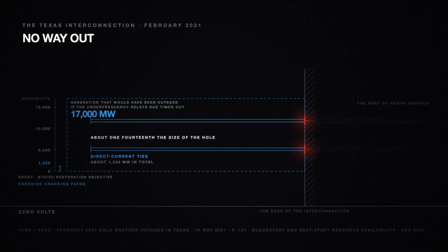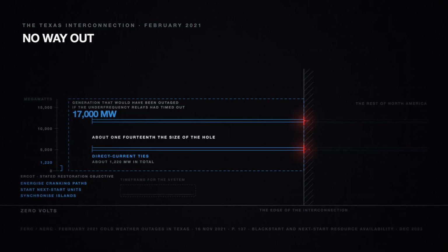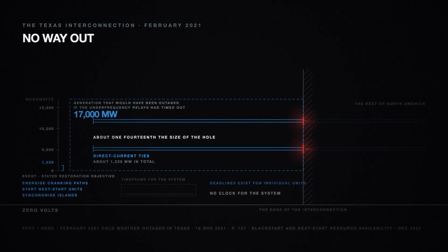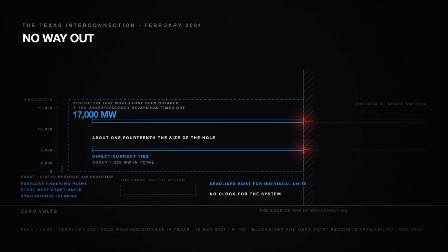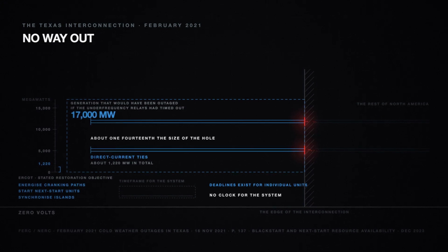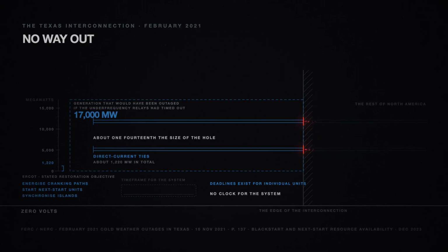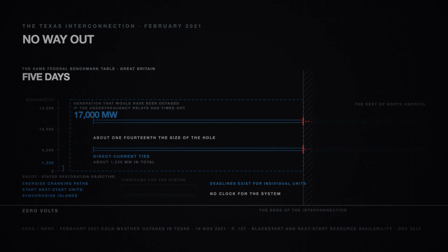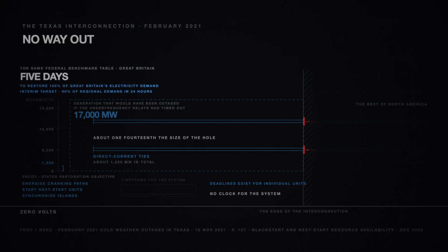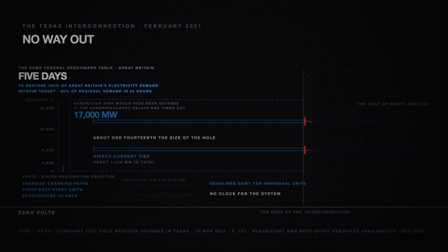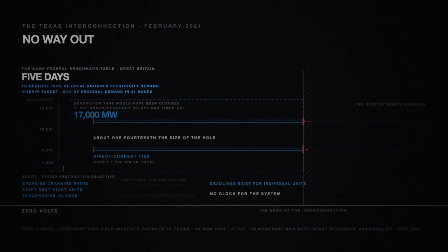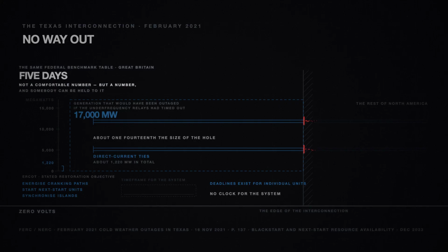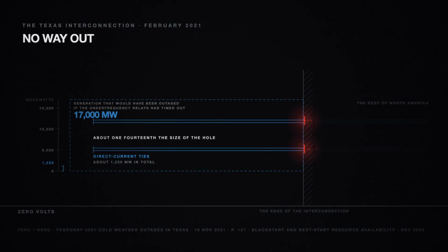There is no answer. The Texas operator's stated restoration objective, energize cranking paths, start next start units, synchronize islands, carries no time frame at all. There are deadlines for individual units. There is no clock for the system. In the same federal benchmark table sits Great Britain's grid operator. Restore 100% of Great Britain's electricity demand within 5 days, with an interim target of 60% of regional demand in 24 hours. 5 days is not a comfortable number, but it is a number, and somebody can be held to it.